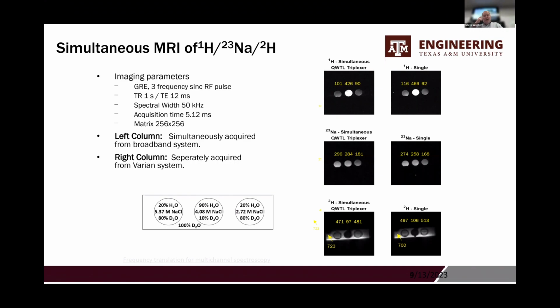And then we repeated this with a different coil, simultaneously proton, sodium, and deuterium, just to show the flexibility of the scanner. So these are all obtained at the same time. And the signal to noise comparison was actually very good. We lost a little on hydrogen because our digitizer was not quite high enough frequency to sample that. We'd undersample. But the other ones we actually did better.